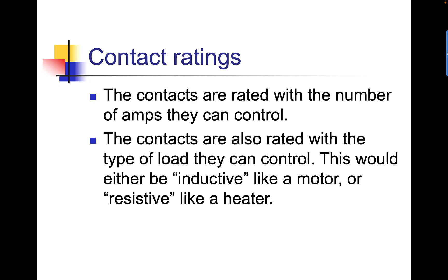The contacts are rated with the number of amps they can control. In other words, how much current you can send through it. The contacts also are rated with the type of load they can control. This would either be an inductive load, like a motor, or a resistive load, like a heater. If it has a coil and produces magnetism, it's considered inductive. If it's just a plain piece of wire or metal that heats up, it's considered resistive.